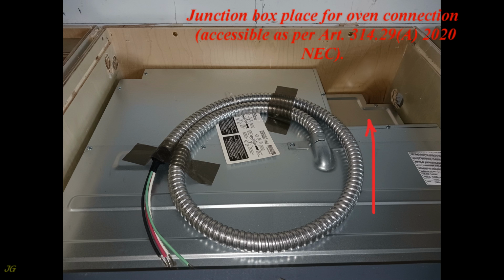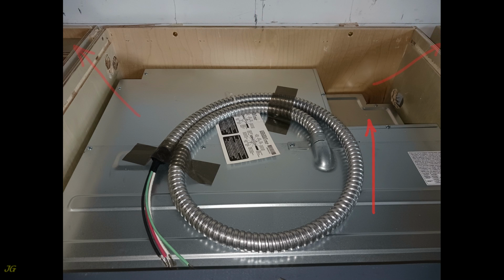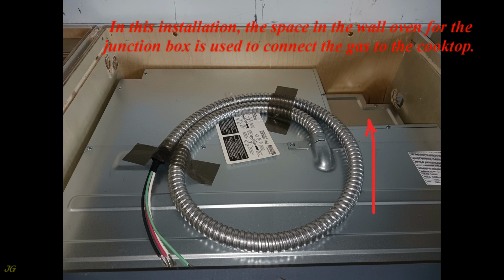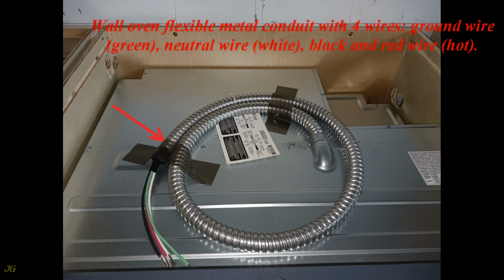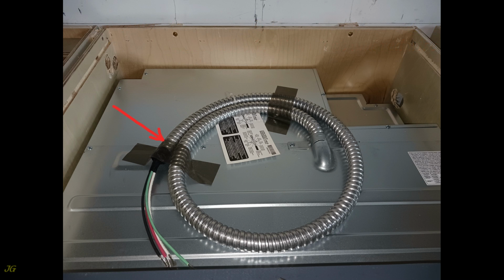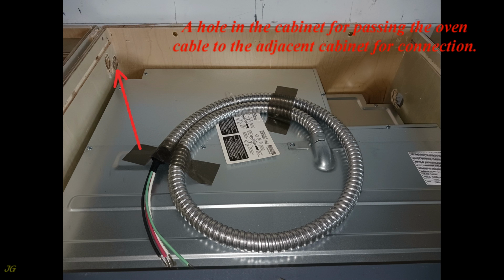Junction box place for oven connection, accessible as per Article 314.29 A, 2020 NEC. The junction box can also be placed in adjacent cabinets. In this installation, the space in the wall oven for the junction box is used to connect the gas to the cooktop. Wall oven flexible metal conduit with 4 wires: ground wire, green; neutral wire, white; black and red wires, hot. A hole in the cabinet for passing the oven cable to the adjacent cabinet for connection.